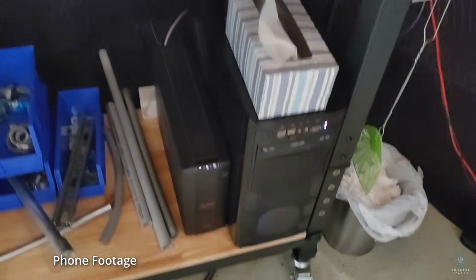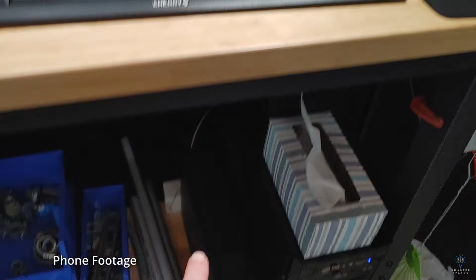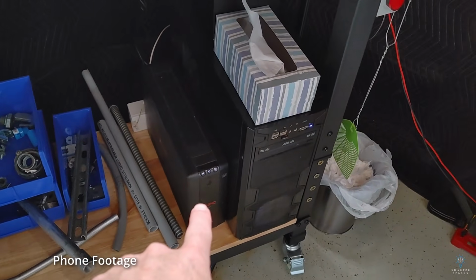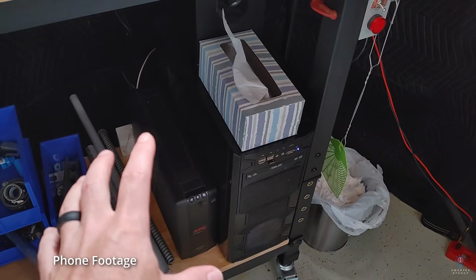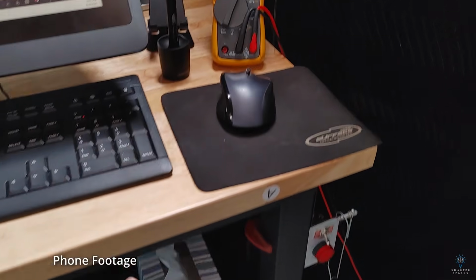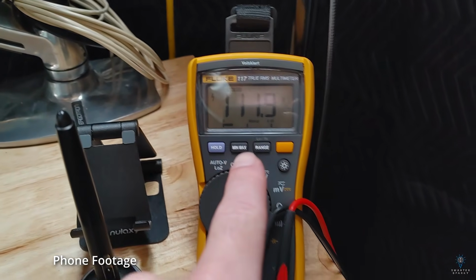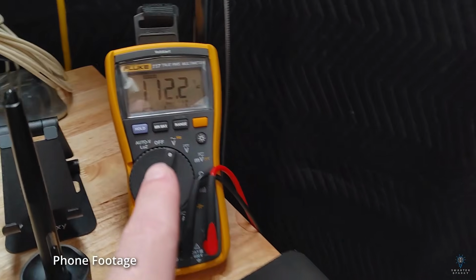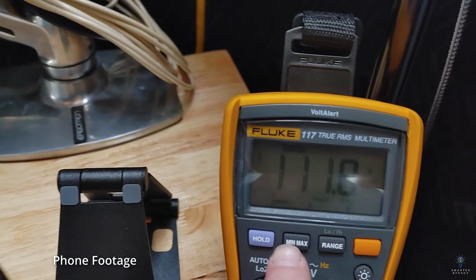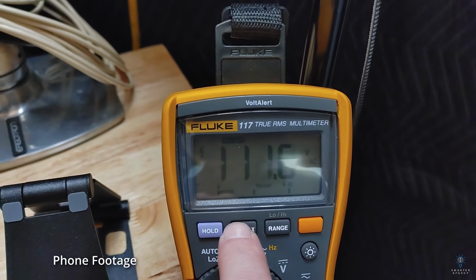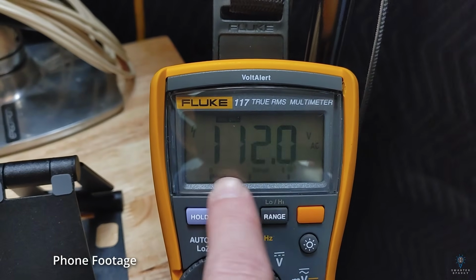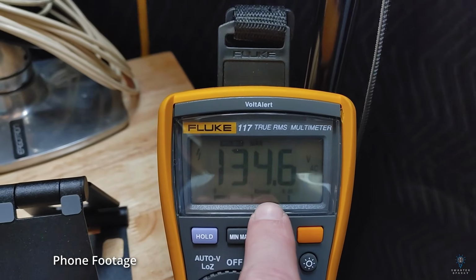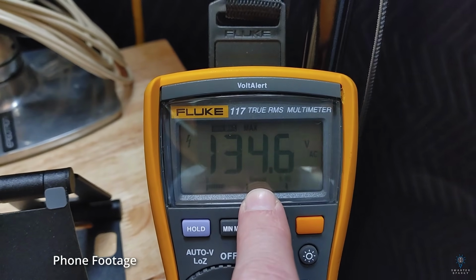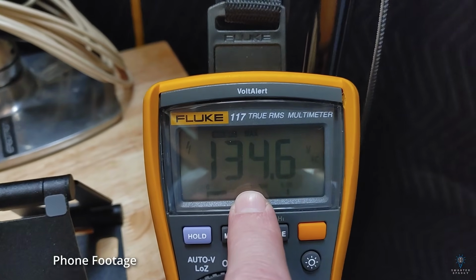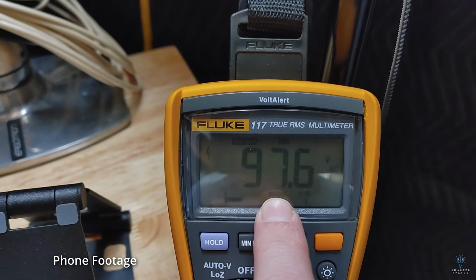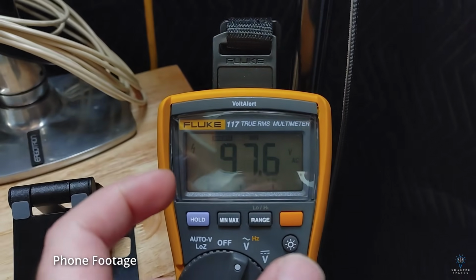So I was just teaching electrical test prep class, and I started noticing my battery backup for my teaching computer has been clicking on and off for the last few hours. So on break, I set up my multimeter and plugged it into a receptacle and set it to read min and max. It's been reading for the last hour and a half now. Right now I've got about 112 volts there, but check out the maximum voltage. Just in the last hour and a half, the max the meter read was 134.6 and the minimum was 97.6 volts. That is a massive voltage swing.